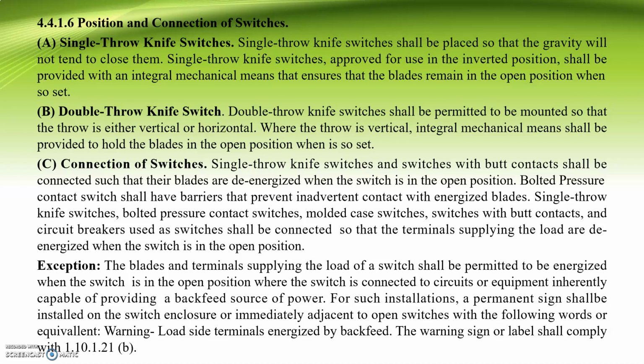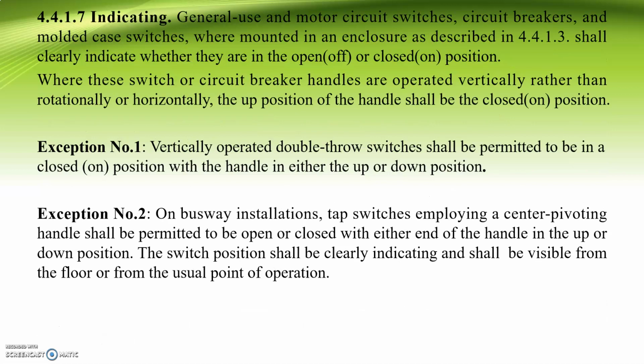For such installations, a permanent sign shall be installed on the switch enclosure or immediately adjacent to open switches with the following words or equivalent: Warning, load side terminals energized by back feed. The warning sign or label shall comply with 1.10.1.21 (b).